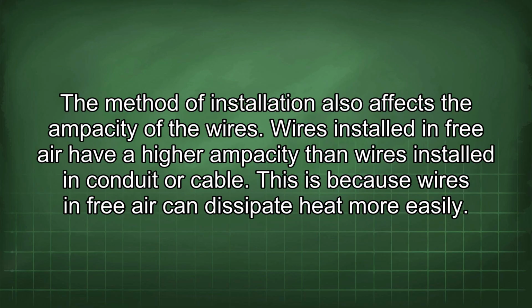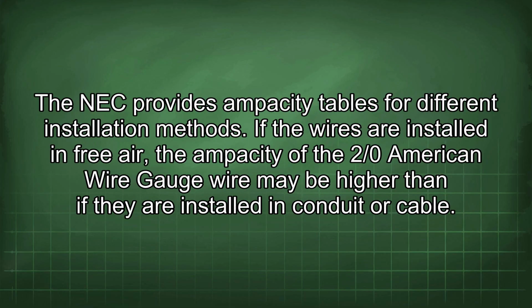The method of installation also affects the ampacity of the wires. Wires installed in free air have a higher ampacity than wires installed in conduit or cable. This is because wires in free air can dissipate heat more easily. The NEC provides ampacity tables for different installation methods. If the wires are installed in free air, the ampacity of the 2/0 American wire gauge wire may be higher than if they are installed in conduit or cable.